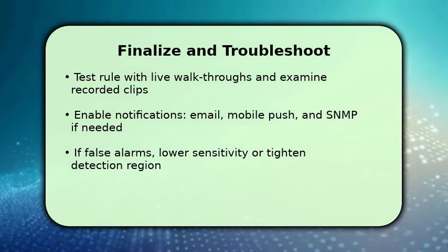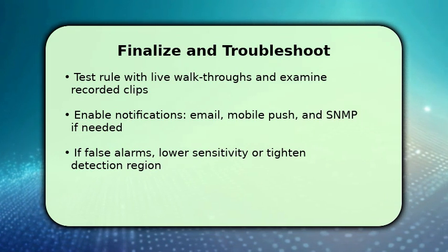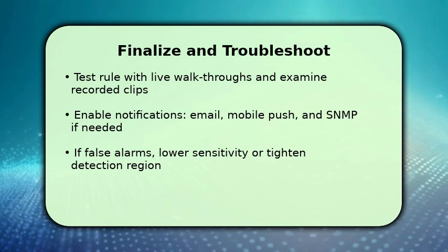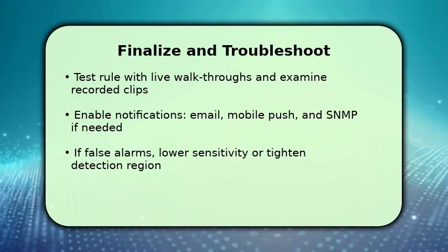If you encounter false alarms, reduce sensitivity, shorten the region, or increase minimum duration. Conversely, raise sensitivity if you miss events. One key troubleshooting tip: check firmware and network latency.